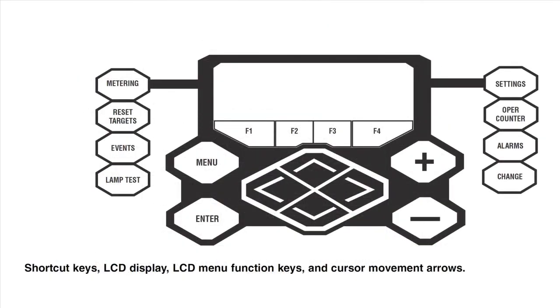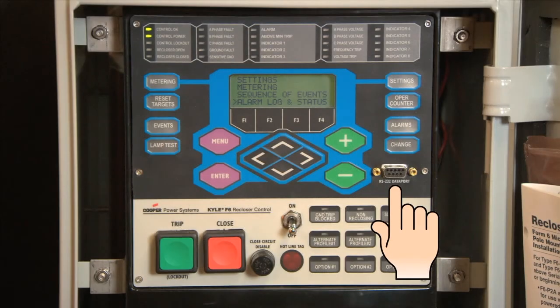The front panel LCD display is used to configure the operating settings for the control. It is also used to display metering, counter information, control parameters, reset alarms, and provide diagnostic information. Control parameters can also be programmed via a personal computer connected to the control through the front panel RS-232 port. Control programming, interrogation, and operations are performed with Form 6 ProView interface software on a personal computer.